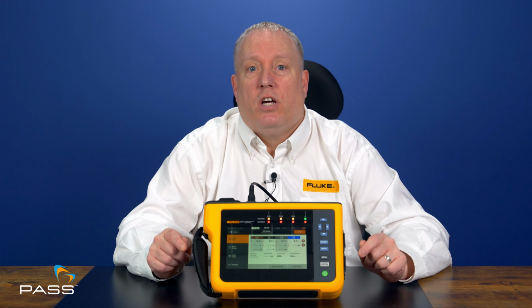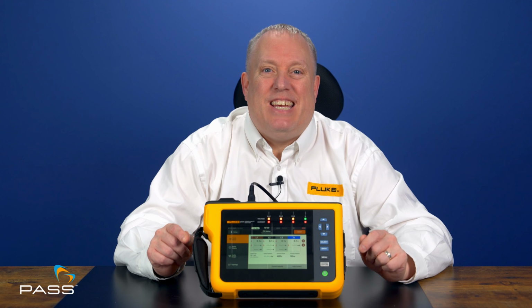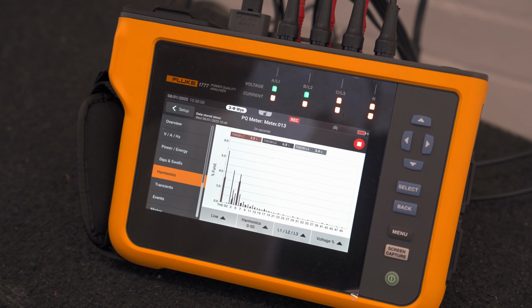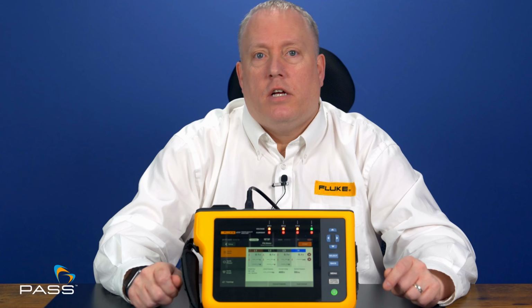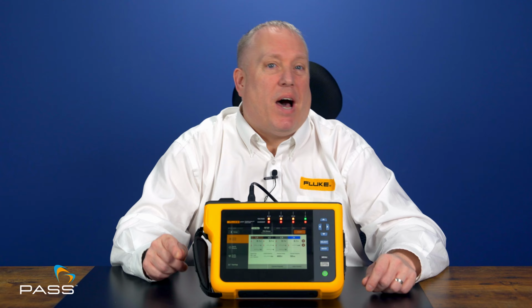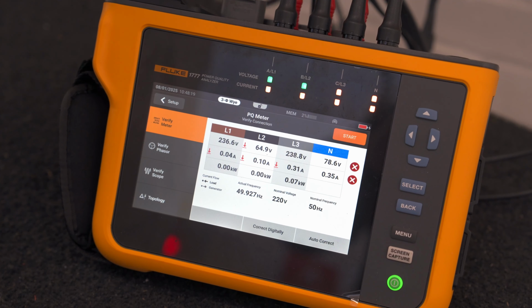Analyze the data: the built-in graphs and reports make it easy to identify low power factor or harmonic issues. Then take corrective action—once you know the issue, you can install capacitor banks, balance loads, or reduce harmonics.